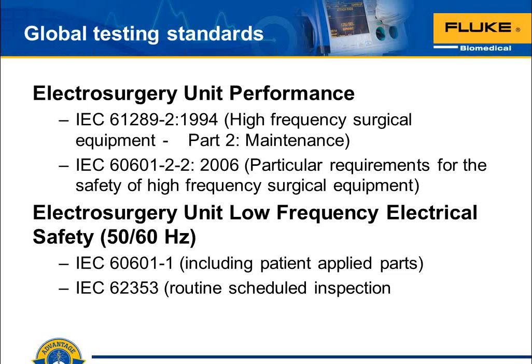The IEC 60601-2-2, 2006, provides particular requirements for the safety of high-frequency surgical equipment. So these are what I'll call minimum performance and safety standards. They technically are voluntary, but if a manufacturer is not adhering to them, they're going to have a hard time getting their FDA clearance to market their ESU here in the United States.